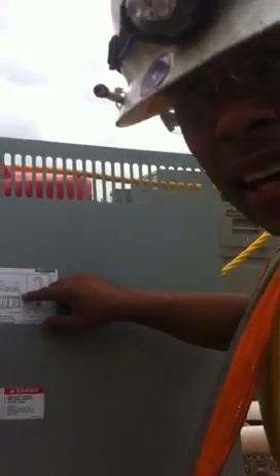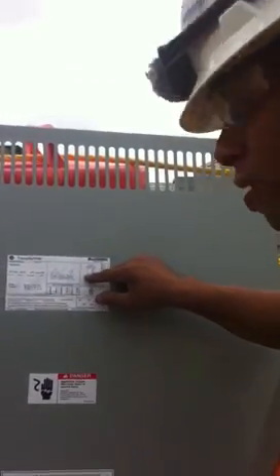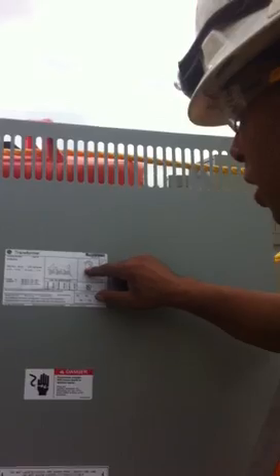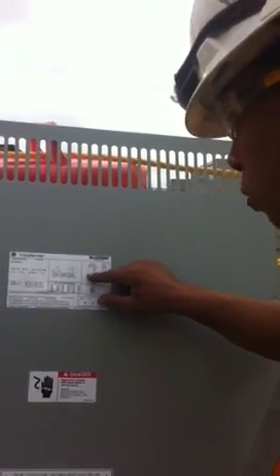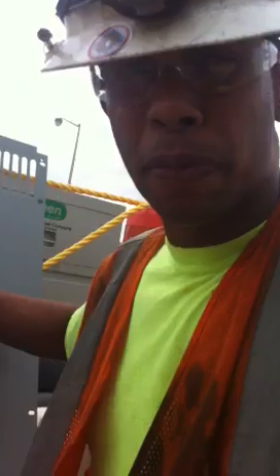We're going to bond X0 — that's our goal. It's on the number three tap. You read taps from highest to lowest. We're going to go to the number three tap, which is 480. But for our purpose, we're just going to focus on the bonding of the transformer.